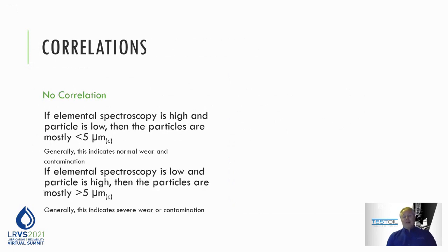Now, if we flip this around, what if your elemental spectroscopy is low, but the particle count is high? Then you're probably dealing with a lot of larger than 5 micron particles, and that is generally expected to be more indicative of severe contamination, which ultimately leads to severe wear. Now, as I said, sometimes they don't correlate. Both of these examples are not moving in the same direction, and like I said, there is something you can learn and take away from that.